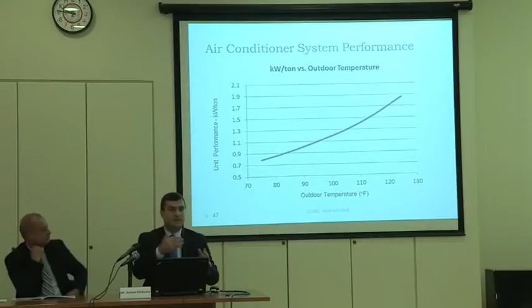We measured ducted split units at 46 degrees C, and you could see the shift between 35 and 46. We are losing about 25–30% efficiency. So we lost already efficiency by this amount for the ducted split when you go from 35 to 46. And you can see that the data points depend on the design of the machines. These are for many machines. They're close to each other, so you could really put a trend in there.